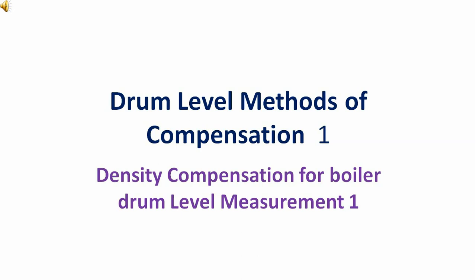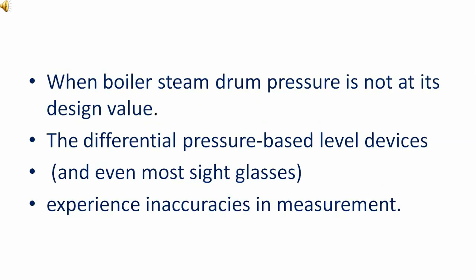Today's topic is drum level methods of compensation. There is another name for this topic, that is density compensation for boiler drum level measurement. When boiler steam drum pressure is not at its design value, the differential pressure based level devices and even most sight glasses experience inaccuracies in measurement.